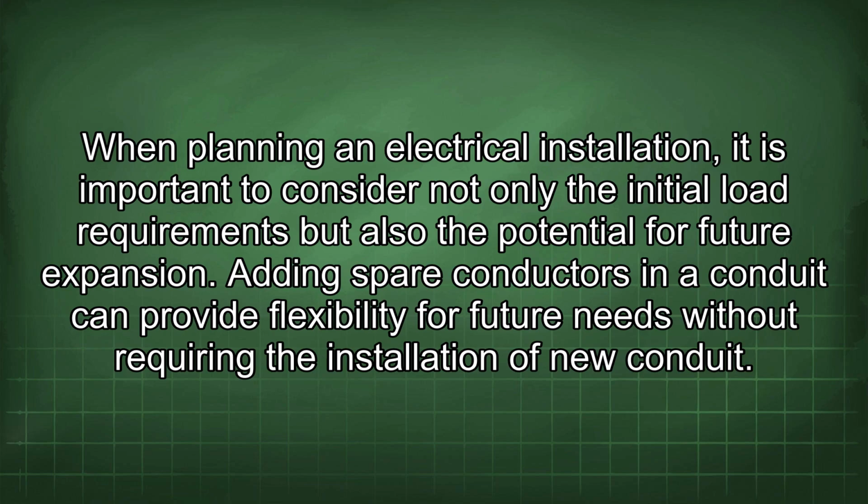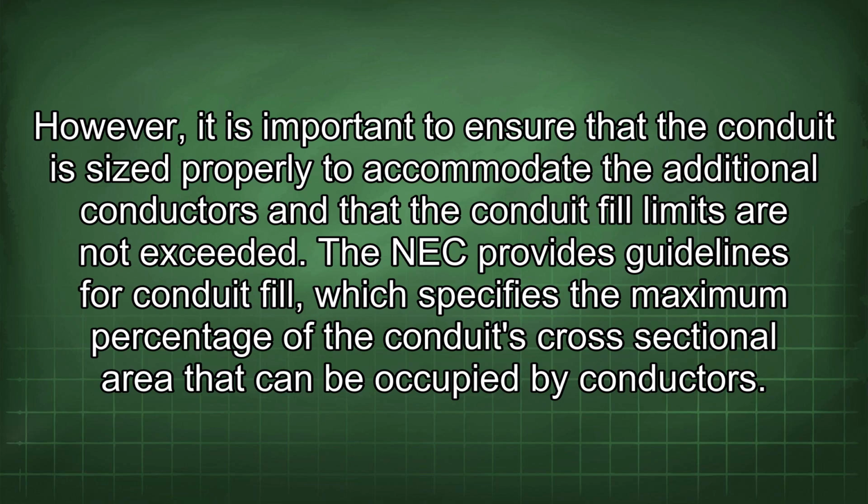When planning an electrical installation, it is important to consider not only the initial load requirements but also the potential for future expansion. Adding spare conductors in a conduit can provide flexibility for future needs without requiring the installation of new conduit. However, it is important to ensure that the conduit is sized properly to accommodate the additional conductors and that the conduit fill limits are not exceeded.